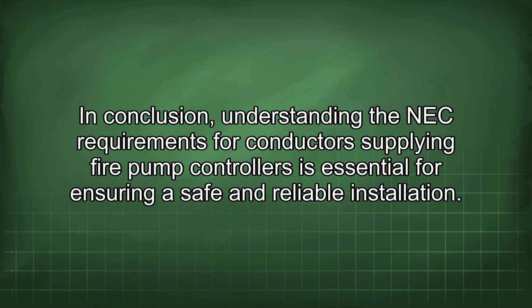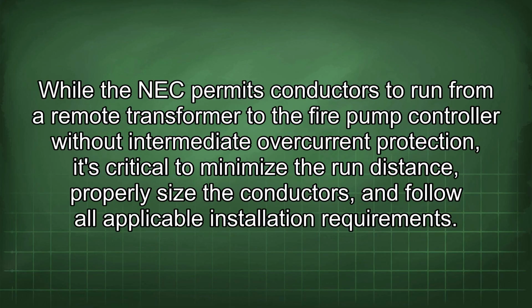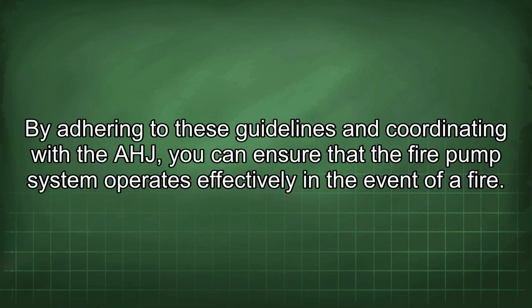In conclusion, understanding the NEC requirements for conductors supplying fire pump controllers is essential for ensuring a safe and reliable installation. While the NEC permits conductors to run from a remote transformer to the fire pump controller without intermediate overcurrent protection, it's critical to minimize the run distance, properly size the conductors, and follow all applicable installation requirements. By adhering to these guidelines and coordinating with the AHJ, you can ensure that the fire pump system operates effectively in the event of a fire.